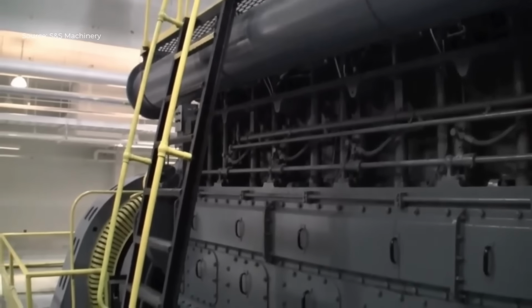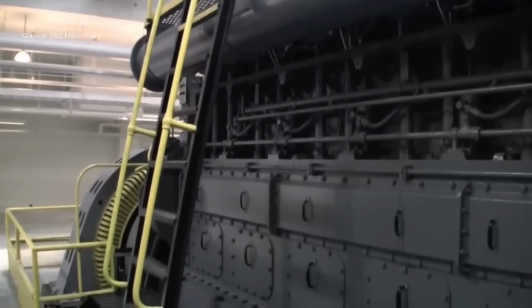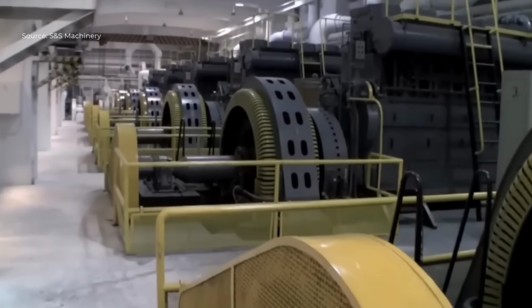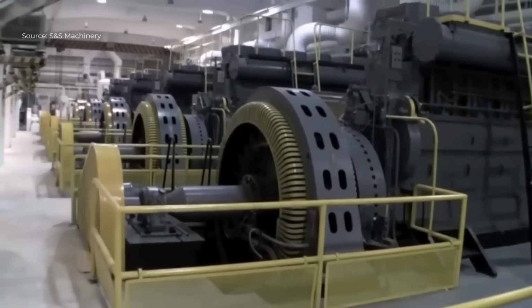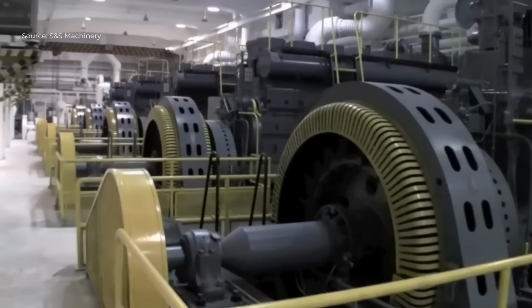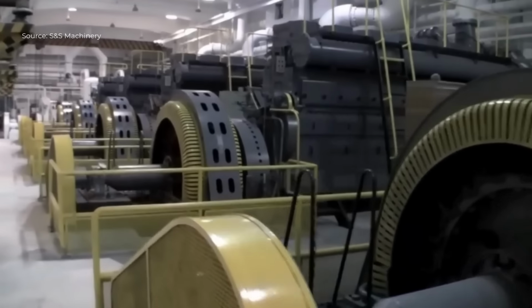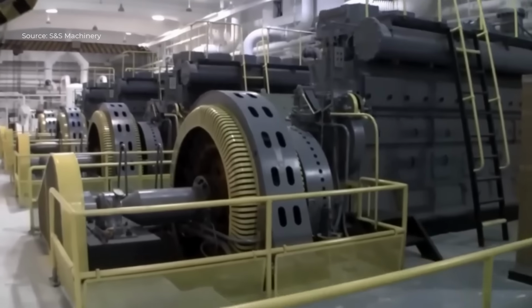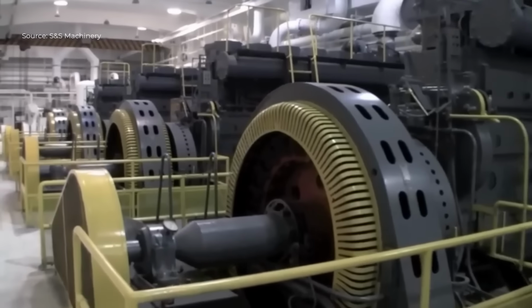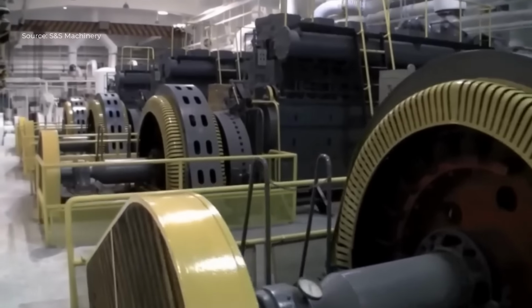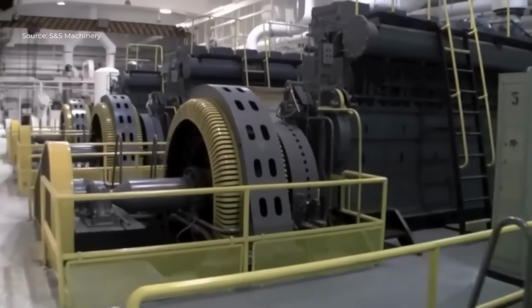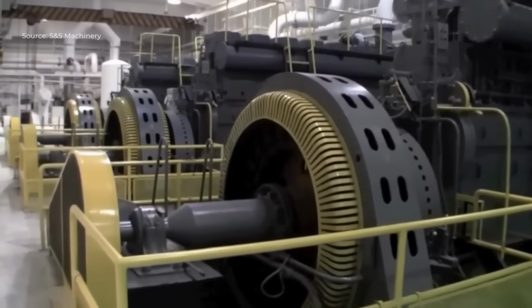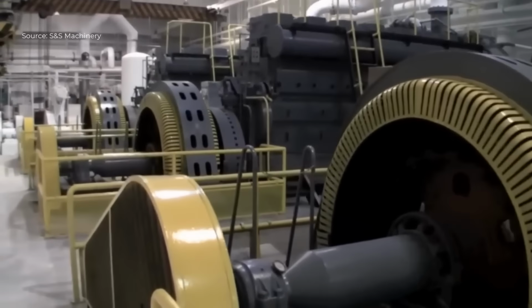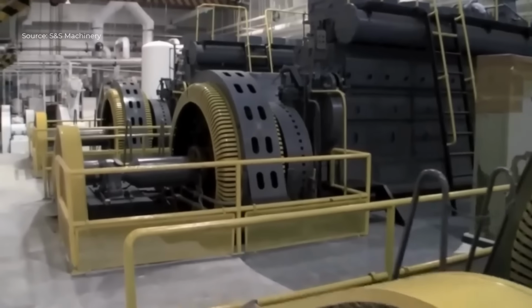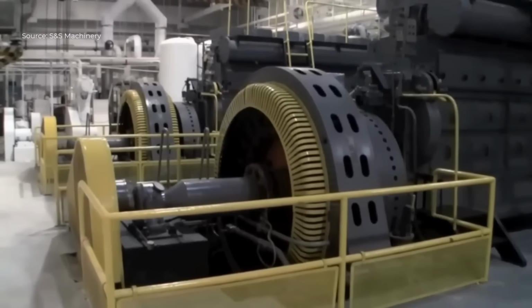Each engine is directly coupled to an electric machinery generator rated at 1.25 megawatts, forming 6 independent generator sets. Together, they deliver a combined output of 7.5 megawatts, enough electricity to supply power to more than 11,000 homes. The attached generators are horizontal synchronous machines, each rated at 1,563 kVA, with an operating voltage of 400 volts, ensuring stable frequency and voltage control for sensitive loads.